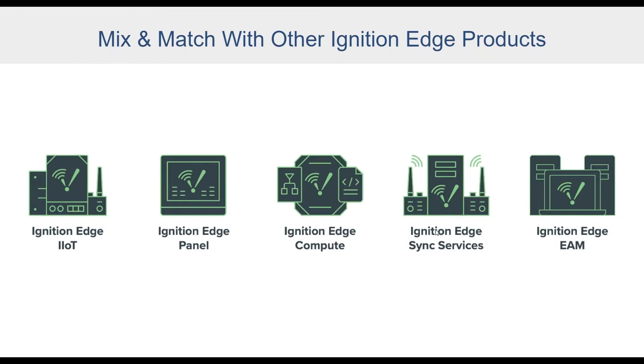If it's not a central Ignition system you're publishing data to and you want to publish in an open source way, that's what Ignition Edge IIoT is for. It takes data and publishes it via MQTT — either to a centralized Ignition system or to a broker, which any business application supporting MQTT can subscribe to. This decouples your infrastructure from your applications. Edge IIoT also allows third-party systems to connect to Ignition Edge IIoT as an OPC server.